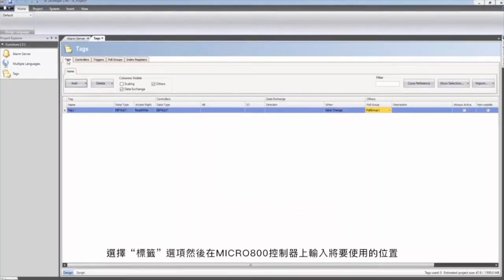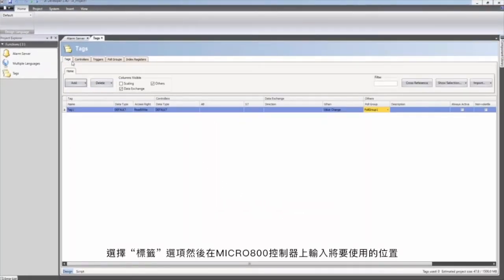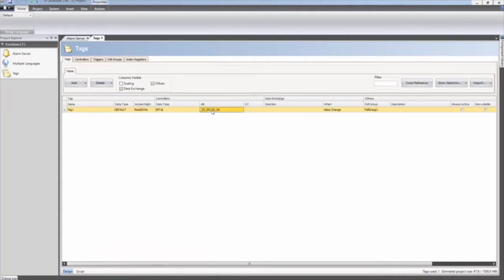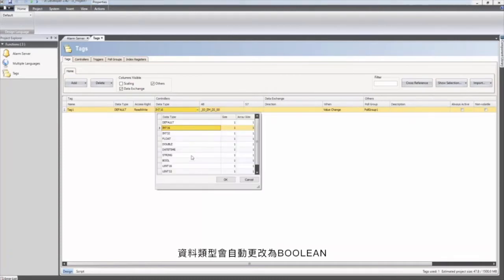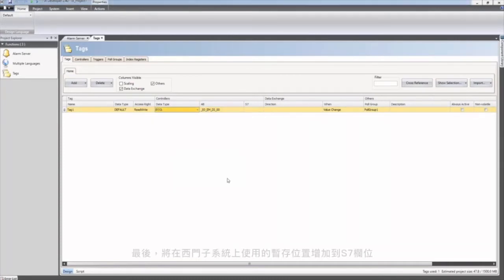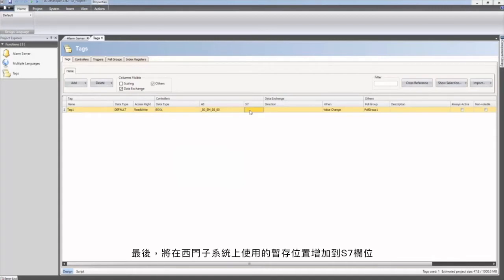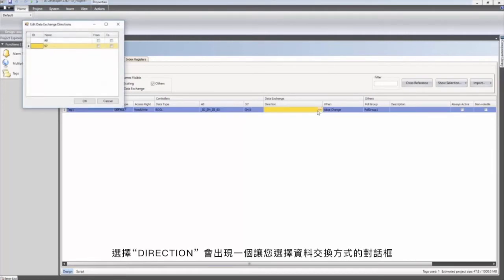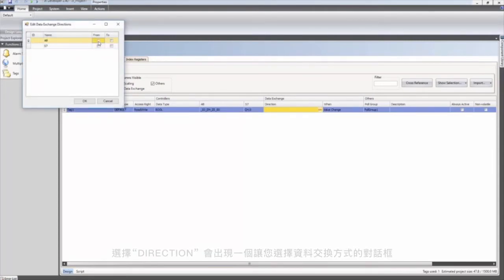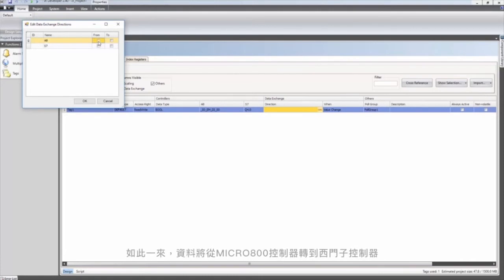The tags tab is selected, and then the address that should be used in the Micro 800 controller is typed in. The data type is automatically changed to boolean. Finally the address that should be used in the Siemens system is added to the S7 column. Select the direction column. A dialog will appear that allows you to select how the data should be exchanged. In this case the data will be moved from the Micro 800 to the Siemens controller.